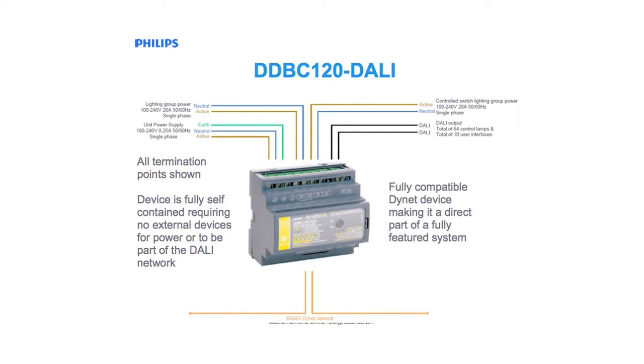Here is a single-line example of how the DDBC 120 DALI can be wired. At the top left-hand side are the active supplies to the device. The unit requires a mains supply at 0.25 of an amp to power the internal electronics. There is an option of a second supply to a 20 amp power relay. This relay is used to remove the standby current consumption of the light fittings. The unit will automatically open the relay when all of the lamps within its universe have been dimmed to 0%.